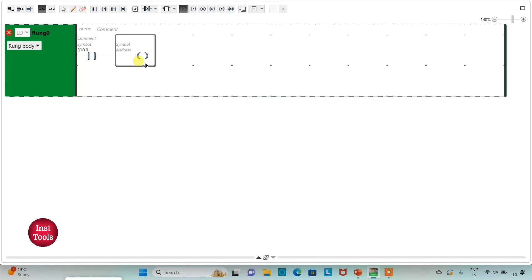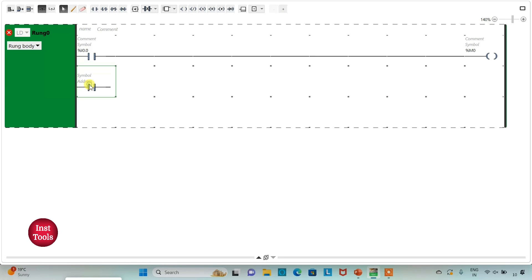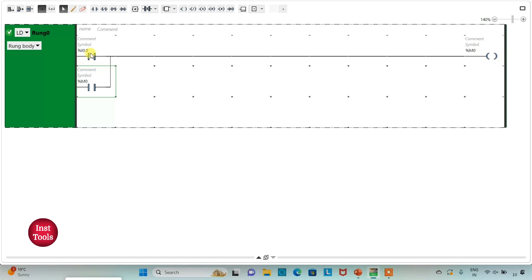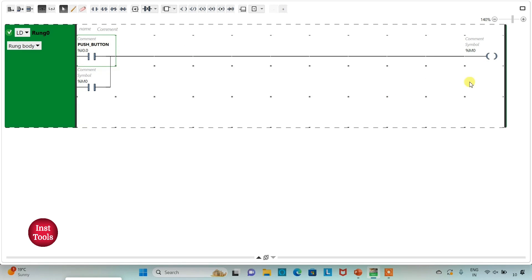Then I will insert a coil and assign address M0 to it. After that I will insert one more normally open contact, connect it in parallel, and assign address M0 to it as well — this creates the self-latch. I will also add the symbol 'button' to the normally open contact I0.0. So when the push button is pressed, M0 will turn on, and when it is released, M0 still remains on.